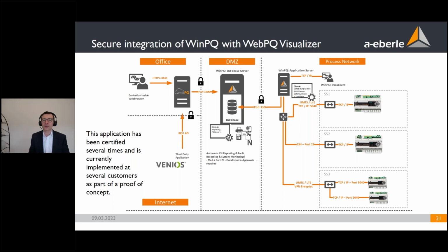What does that mean in the standard parameterization? Standard parameterization means 800 measures are metered inside this device and stored in a really small way, and then the application reads out the data in a way that does not require a really high data rate. We have applications running over SHDSL technology, which from time to time has data rates of only approximately 100 kilobit per second. Even in this application we have to bring the oscilloscope sample values, as well as the long-time evaluation records, into the database absolutely securely, and this is running.